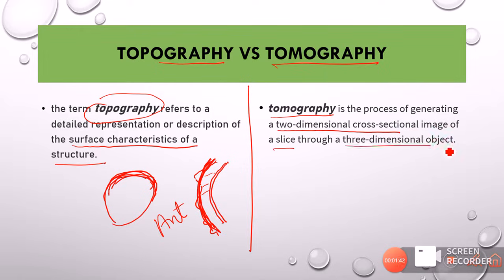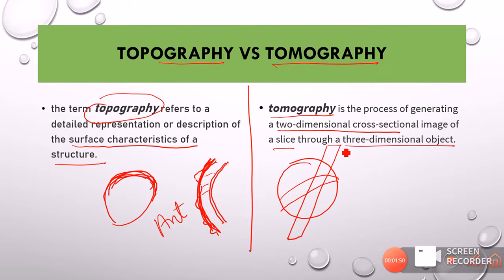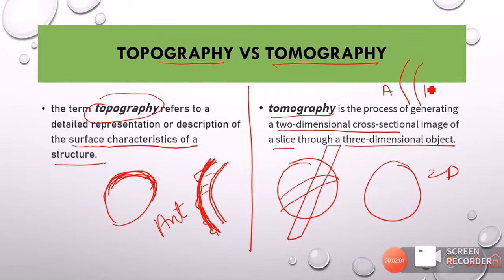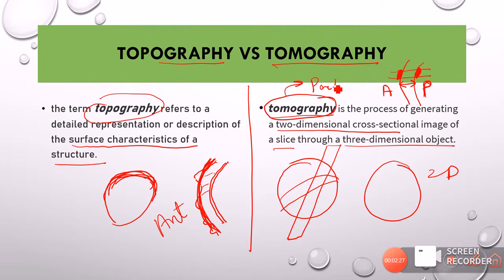Tomography, however, is a process of generating two-dimensional cross-sectional images of a slice through a three-dimensional object. If we have a ball and take a slice through it and look at the 2D image, that is tomography. For the cornea, taking a slice through it allows us to see not just the anterior surface but also the posterior surface, and we can find out the thickness of the cornea by studying the distances between anterior and posterior surfaces. So tomography gives us an important parameter: pachymetry.